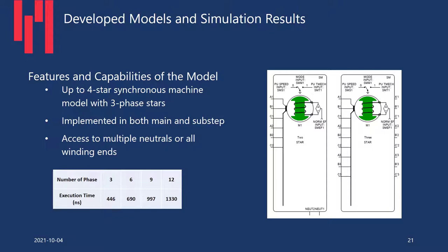Now let's look at the models developed in the RTDS library based on the previous analysis. We have both symmetrically distributed polyphase and multi-star synchronous machines — up to 12-phase or up to four-star three-phase synchronous machine models. They are implemented for both main step and sub-step. You have access to both ends of windings, allowing multiple neutrals. The table shows execution time based on number of phases — even for a 12-phase machine, you can model it in 1.3 microseconds.